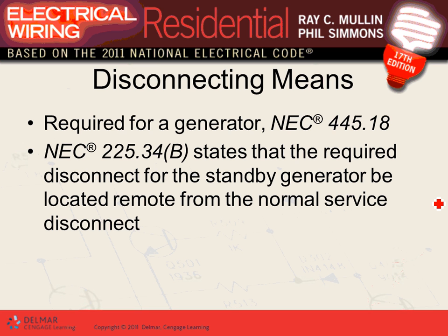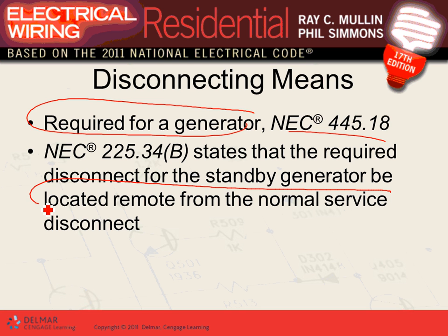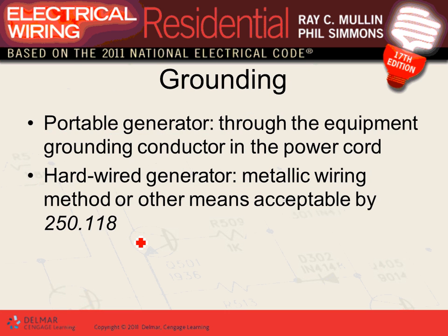Okay, requires disconnect. So you need a disconnect for the generator, guys. A generator requires a disconnect from 445.18. It says that the required disconnect for the standby generator can be located remote from the normal service disconnect. So you can put it remotely from the normal service disconnect. So you have to have a disconnect by the generator. That could be on the generator or within sight of the generator, with some exceptions. So you can't disconnect the power.